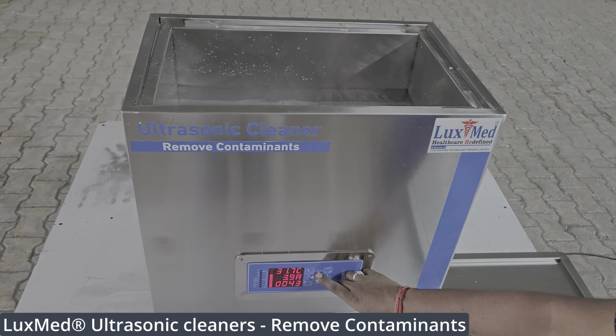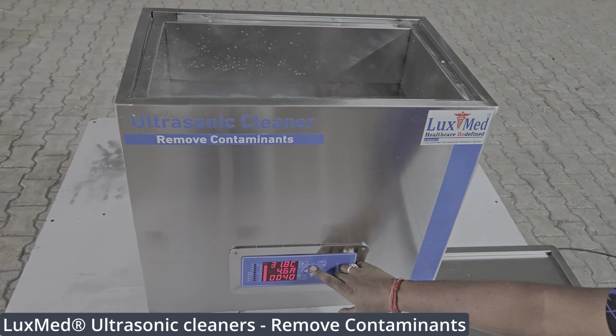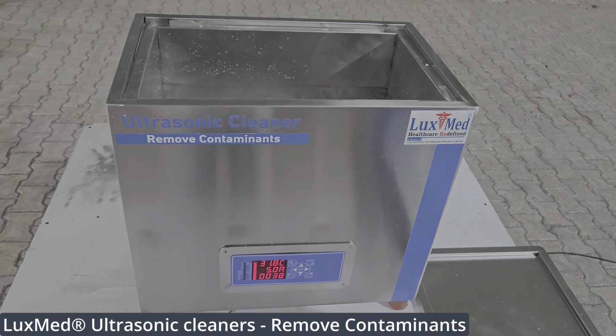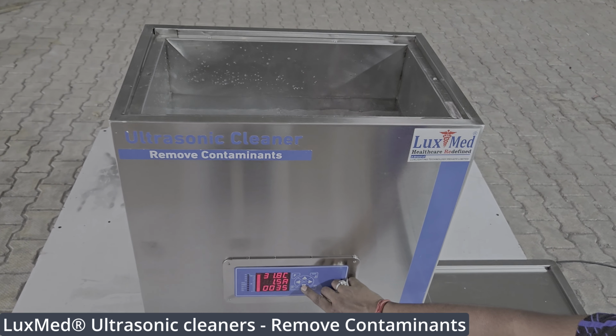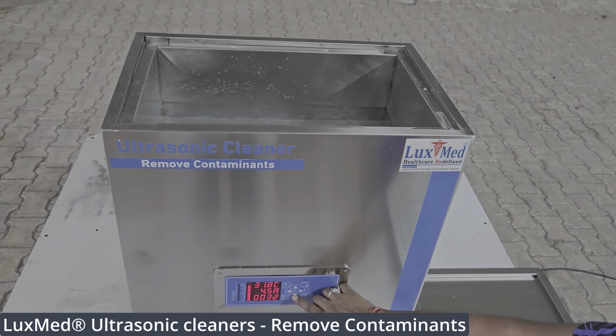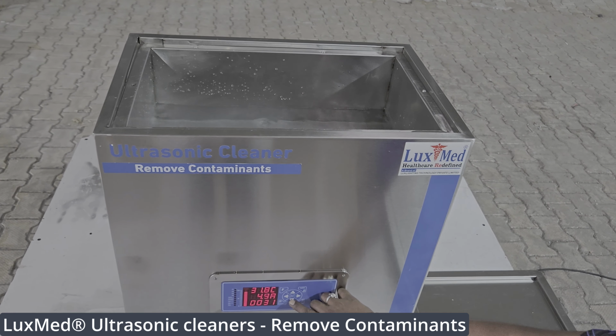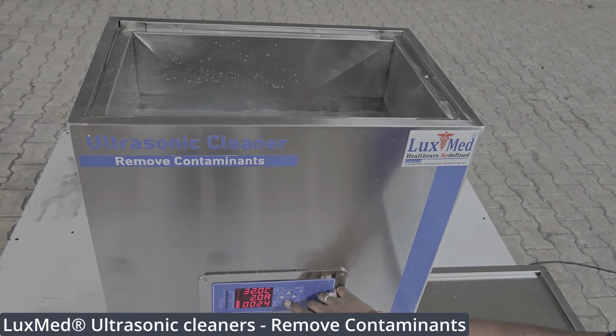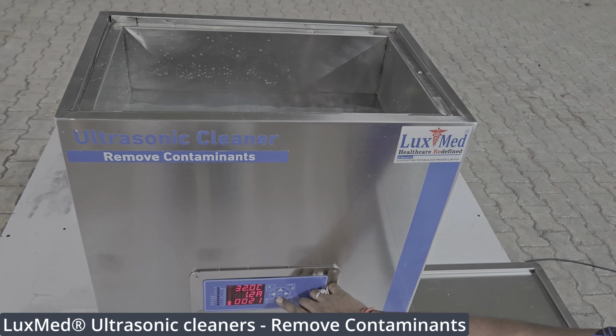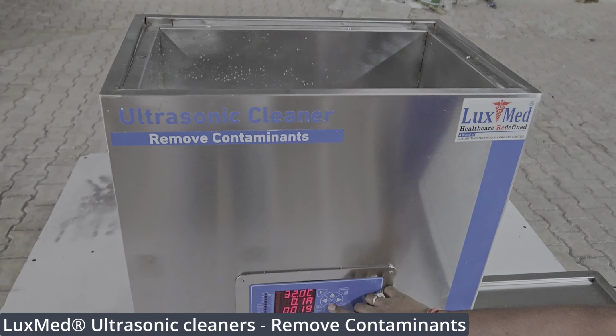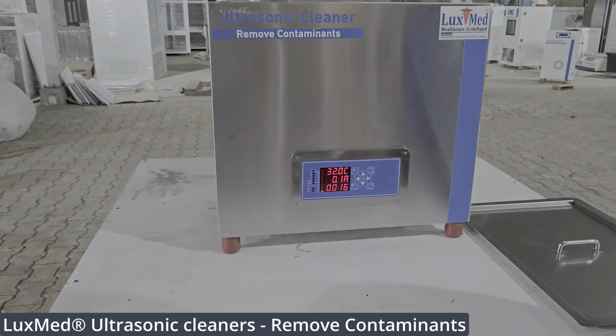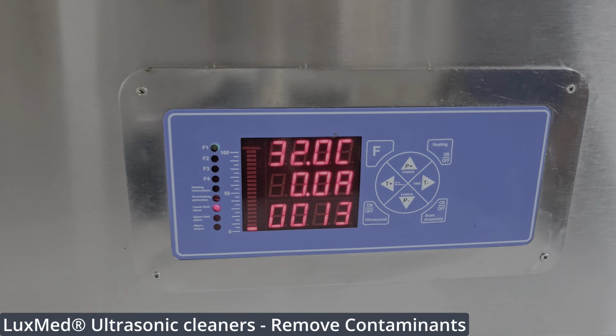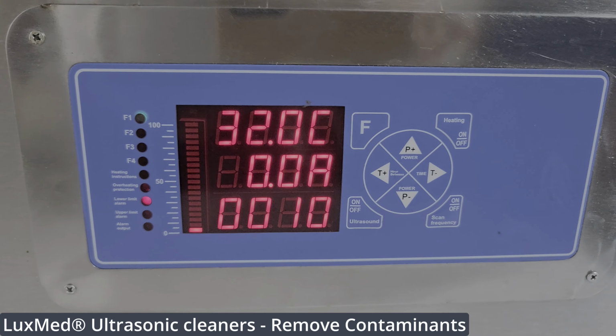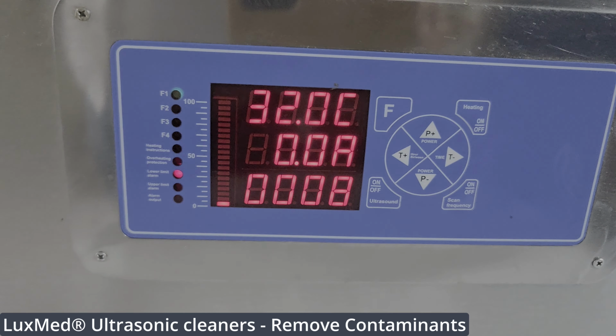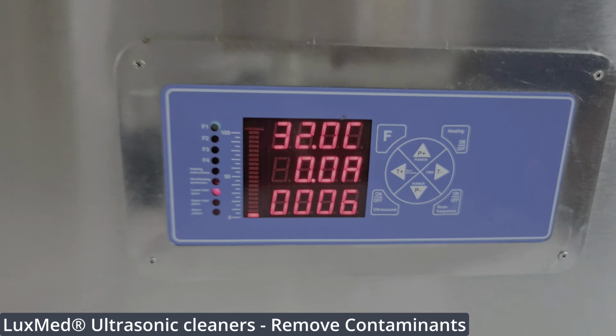Ultrasonic cleaner working principle. Ultrasonic cleaning uses cavitation bubbles induced by high-frequency pressure, sound waves to agitate a liquid. The agitation produces high forces on contaminants adhering to substrates like metals, plastics, glass, rubber, and ceramics. This action also penetrates blind holes, cracks, and recesses. Ultrasonic cleaners work by generating high-frequency sound waves that create tiny bubbles, cavitation, in a cleaning liquid. These bubbles then implode, creating localized shock waves and intense heat that dislodge dirt and contaminants from objects submerged in the liquid. Here's a more detailed breakdown.